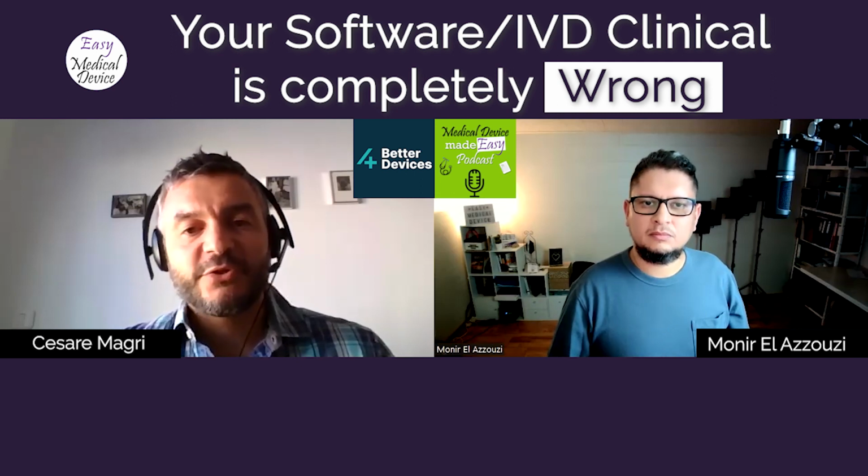First you draft the intended purpose, okay? And then you dig really into a state-of-the-art analysis, but a very systematic one in which you really try to understand how the field works. What is really standard of care in the countries where you are going to sell this product? So how does it really work? What is the terminology? How would you express things so that the users, the doctors, can really understand immediately what you are talking about? And then you reformulate your intended purpose.